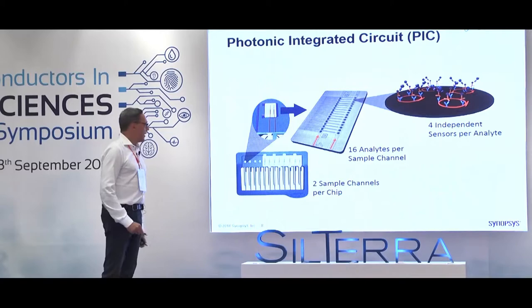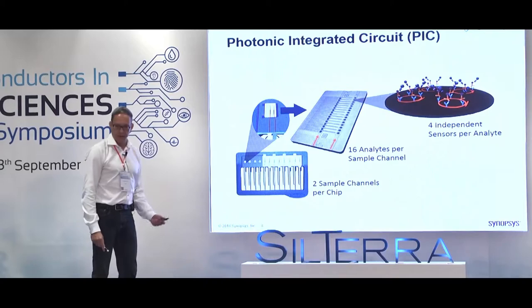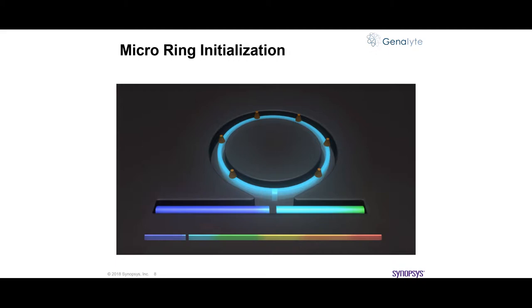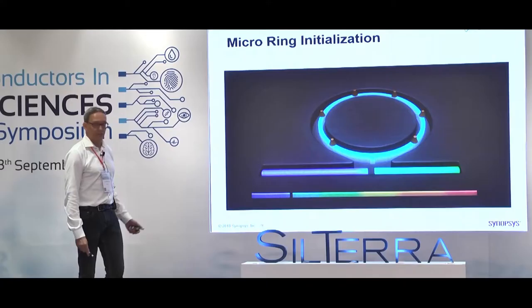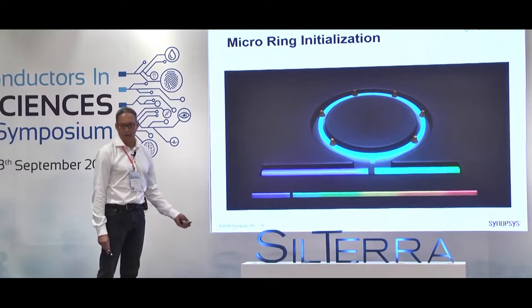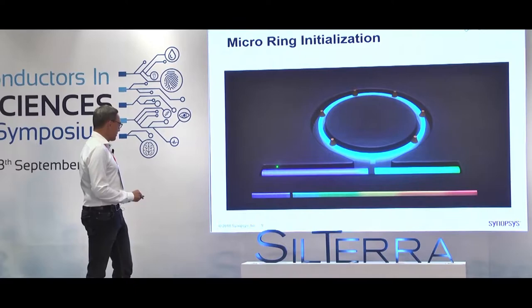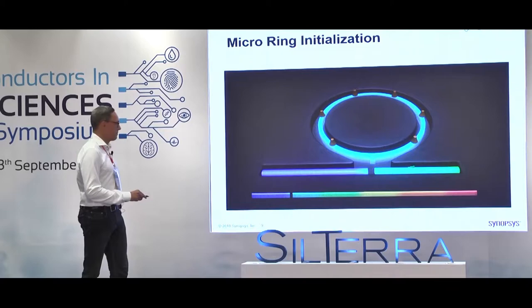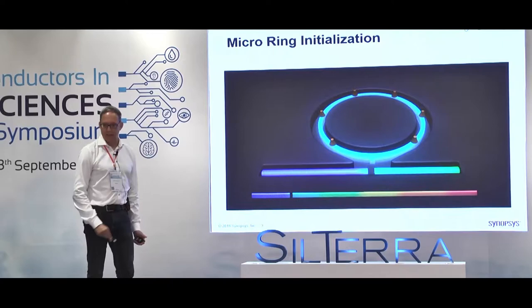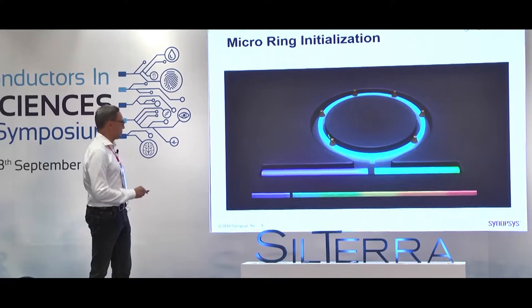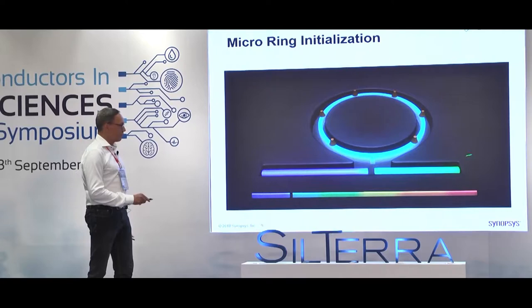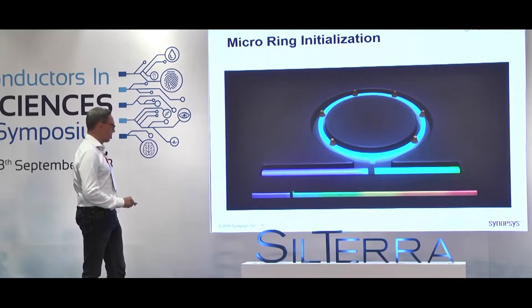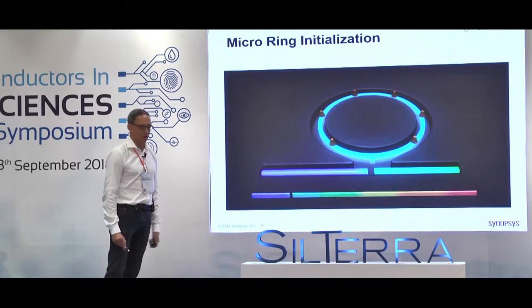You can test 16 different analytes, and each detector consists of four independent sensors. These sensors are based on a component used a lot in integrated photonic circuits: the micro ring resonator. In the micro ring resonator, you can see the ring, and at the bottom a straight channel. In this straight channel you have a whole spectrum of light going through, but the ring only resonates for specific wavelengths of light — in this case it's resonating in the blue light.